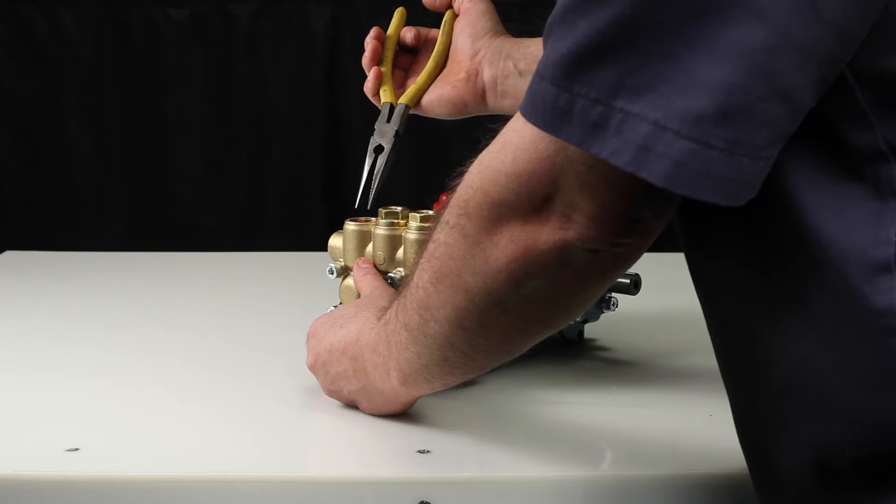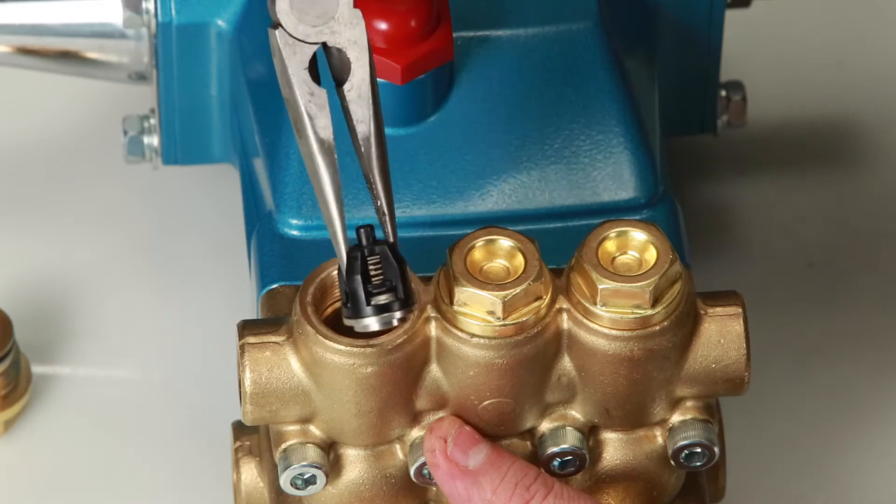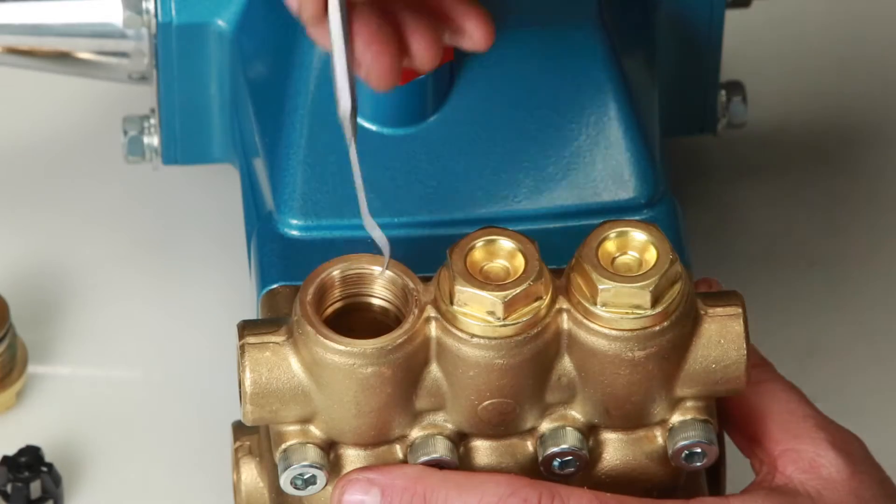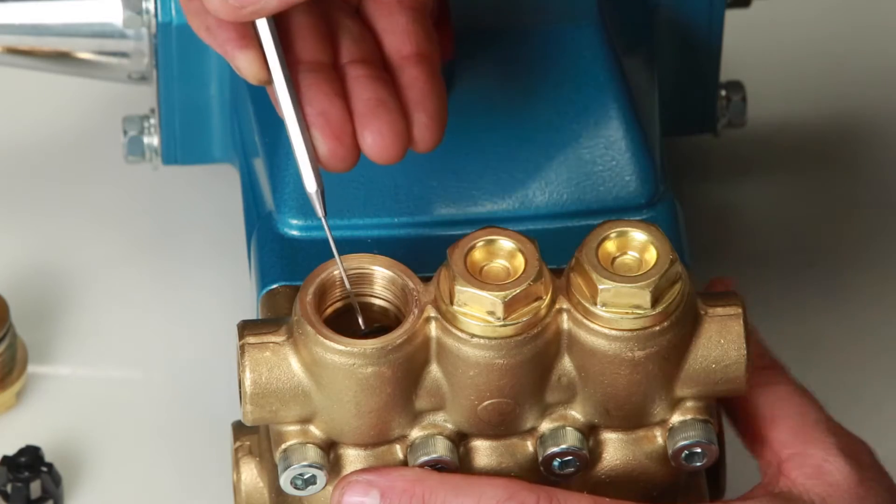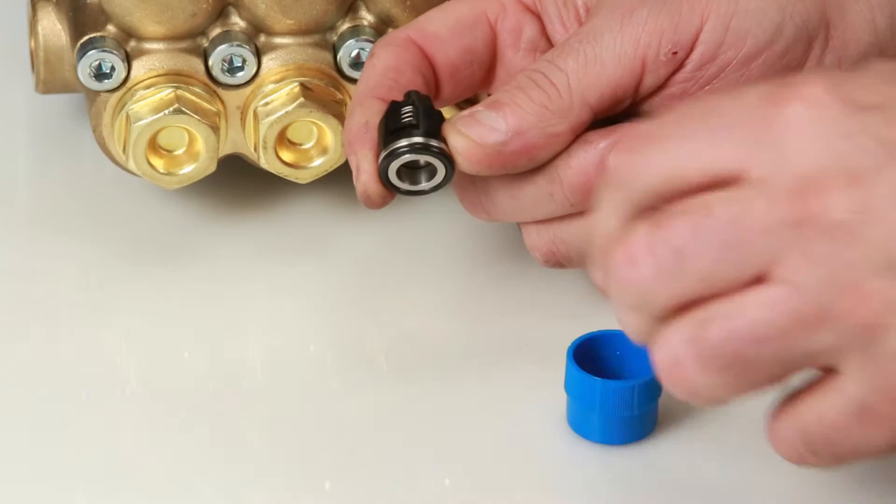To remove the valve assembly, use needle-nose pliers grasping the top of the spring retainer. Give a small twist while pulling away from the manifold to remove. When removing the valve assembly, the O-ring may remain in the manifold. Using a small pick or screwdriver, reach into the manifold to remove.